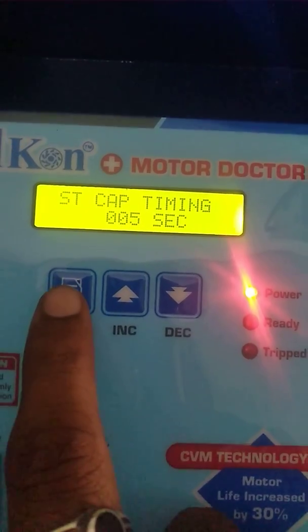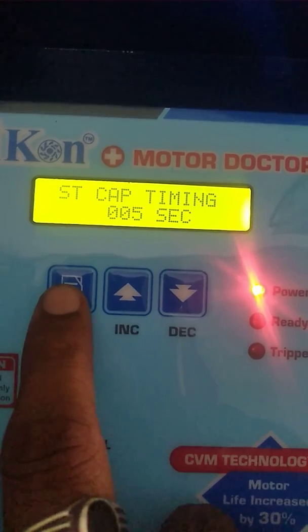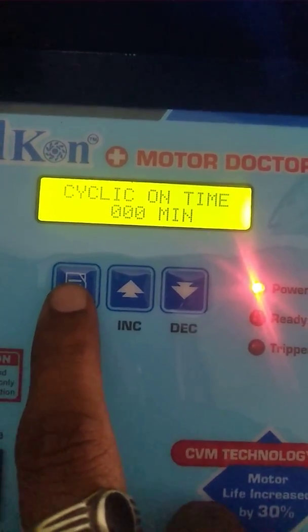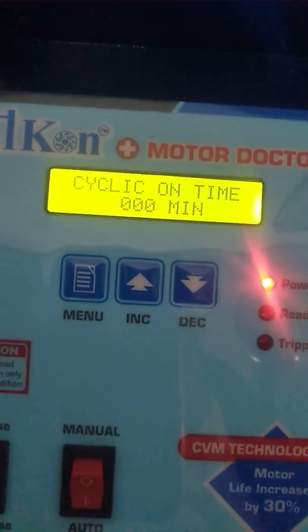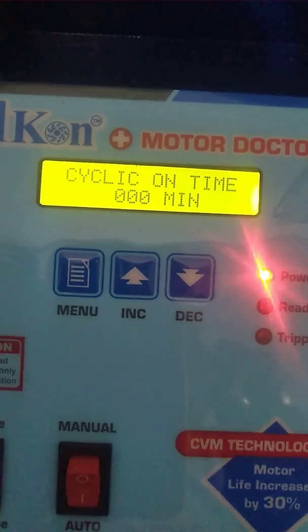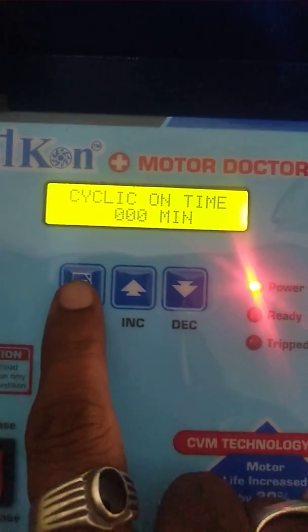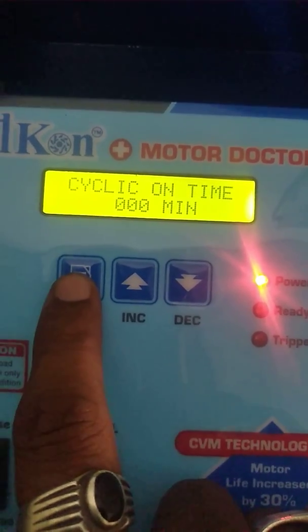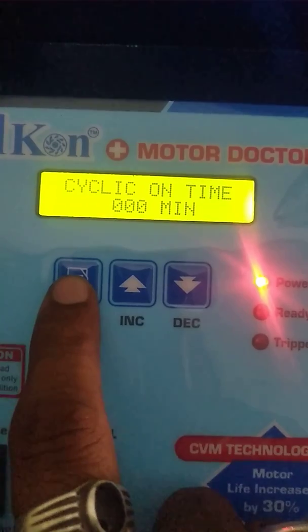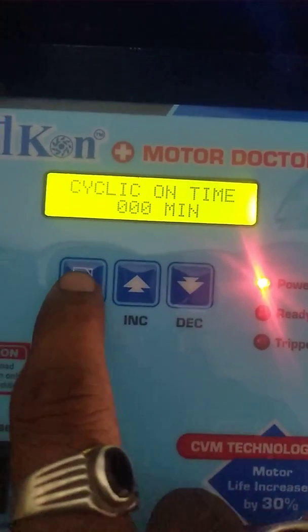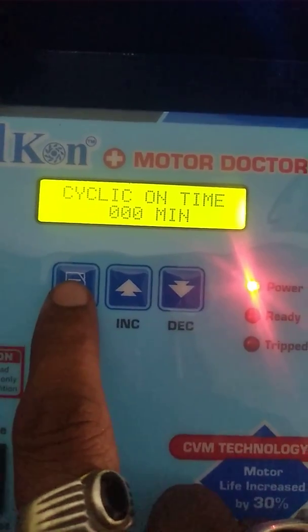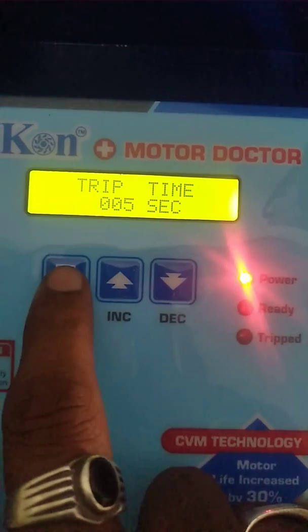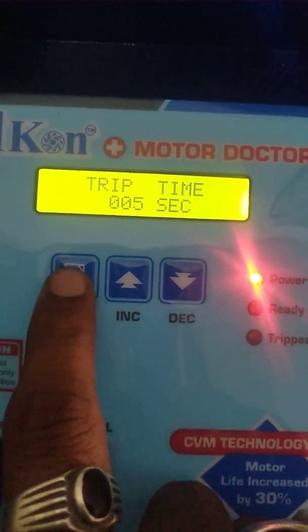Then the starting capacitor — after 5 seconds, the switching capacitor turns off. Then cyclic time: if the panel is used for a borewell compressor and the water is dry, you can set an on-time — suppose one hour is needed — and a cyclic off time. Then trip time: if any problem happens within 5 seconds, the motor gets switched off.